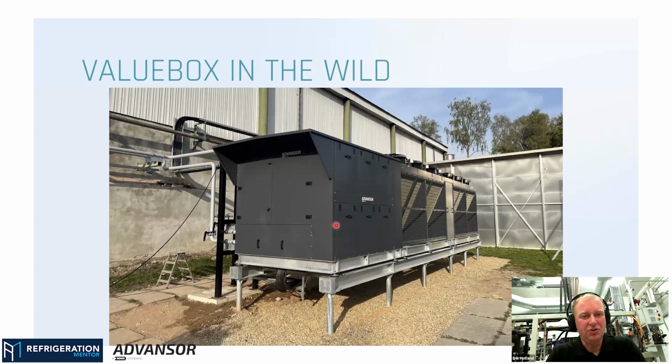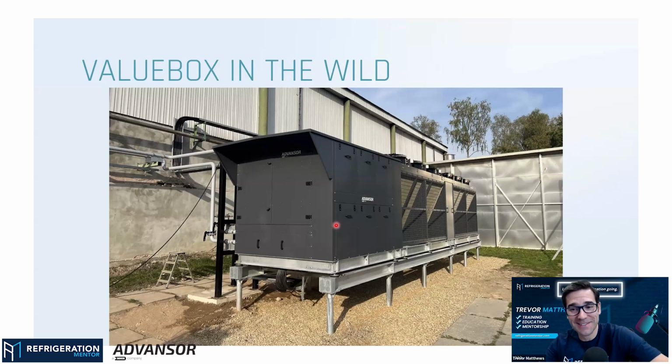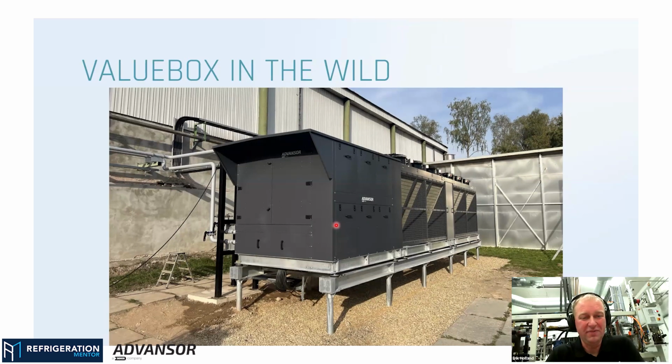An issue we see a lot of times is that the guys get CO2 delivered the day before. A truckload of bottles comes, and they unload it, and it's outside all night. Maybe the temperature drops at night. You may only have 5 degrees at night, or maybe it's freezing sometimes in winter time. Then your CO2 bottles are frozen solid. There's no movement, you have no pressure. It's absolutely next to impossible to get anything out of them.